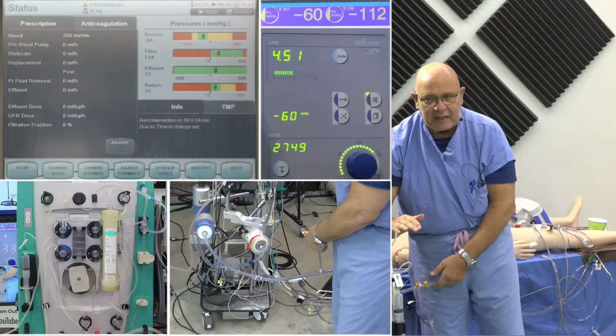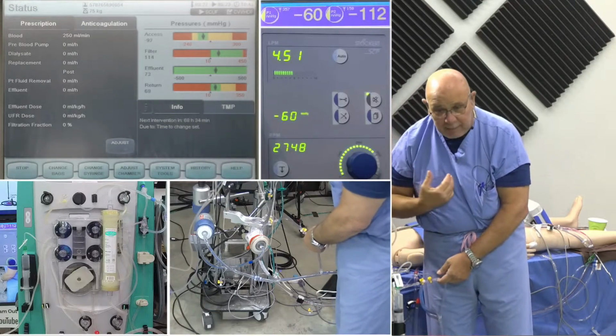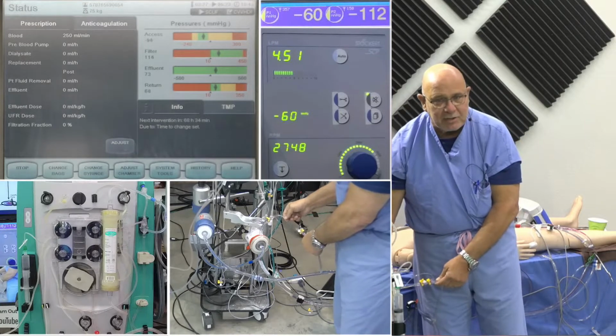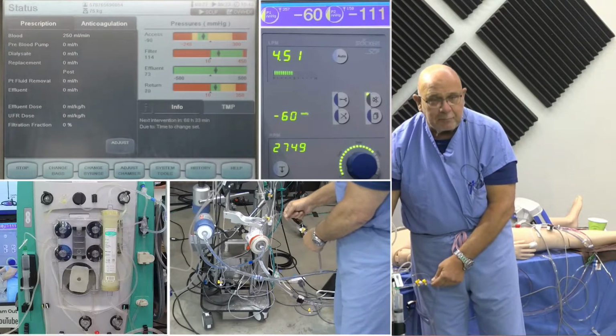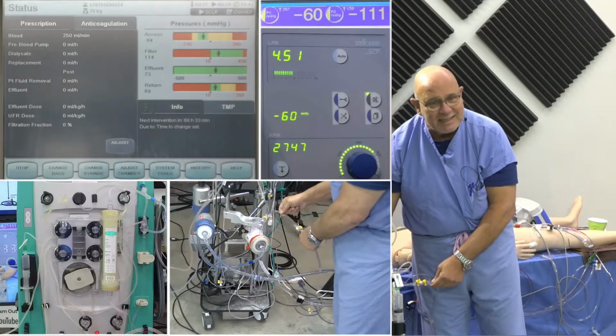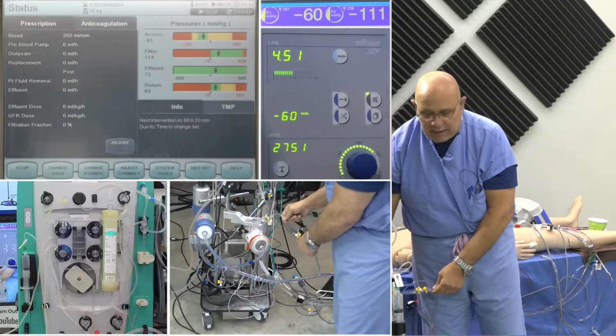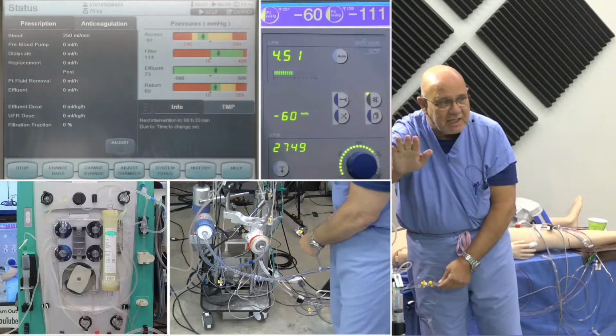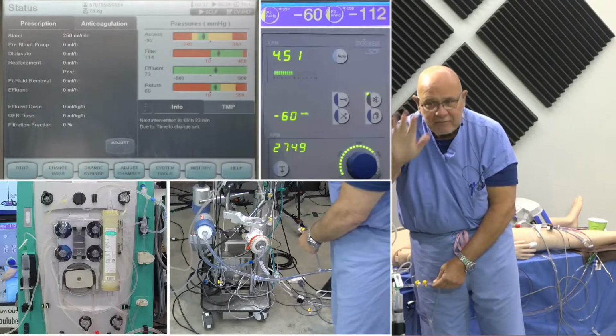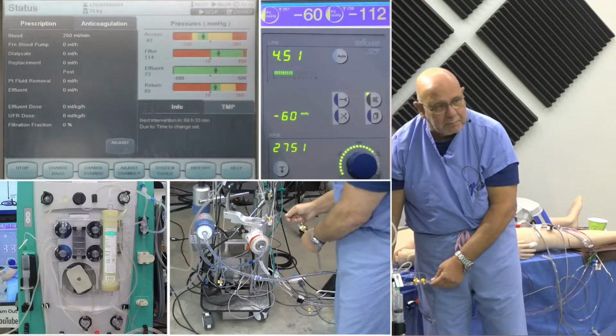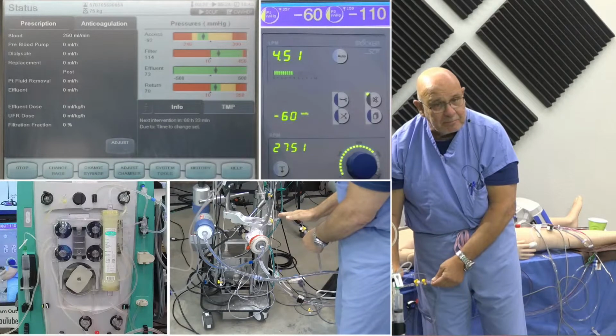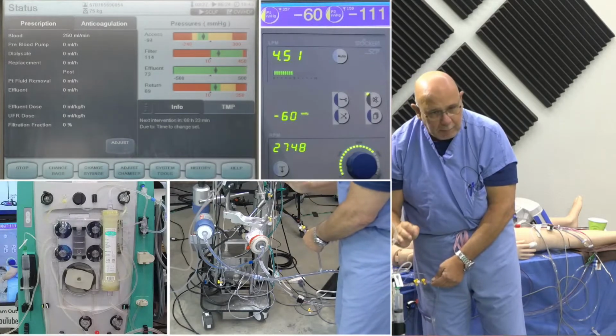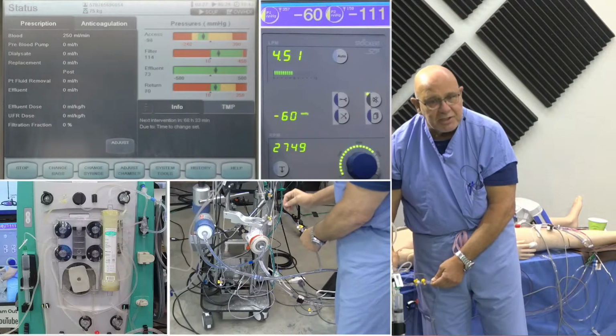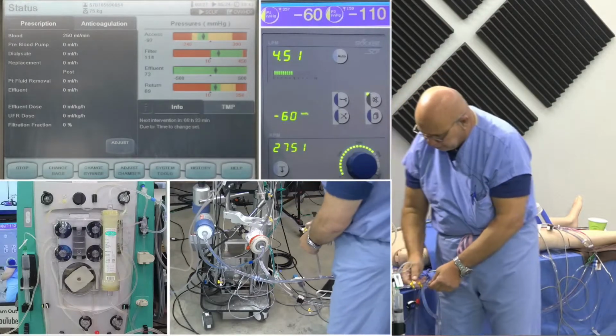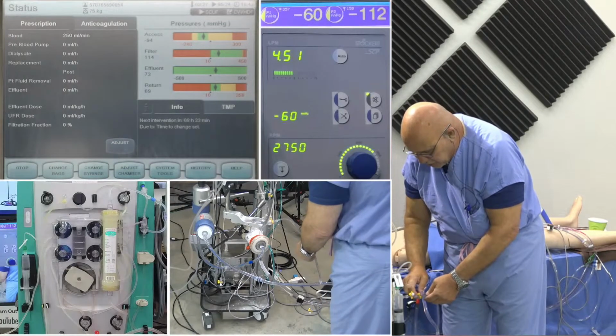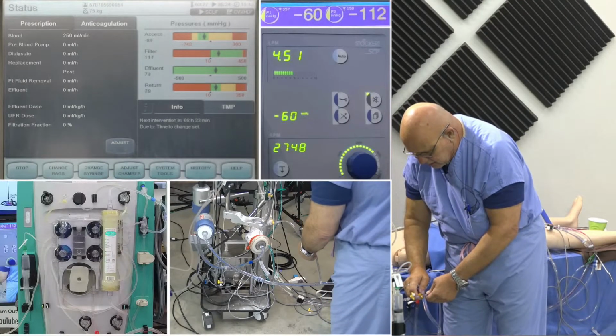But if I'm flowing 250 cc's there and I'm flowing 4.5 liters here, that amount of recirculation is clinically insignificant. And based on, again, my experience, this makes the treatment more effective because it doesn't alarm, it doesn't stop, it doesn't get interrupted, and you can set it to where the CRRT machine sees very physiologic numbers, making it work much, much better. So I accept that there is a level, albeit very small, of recirculation that will naturally occur. Okay, so for right now, I'm going to take this off.